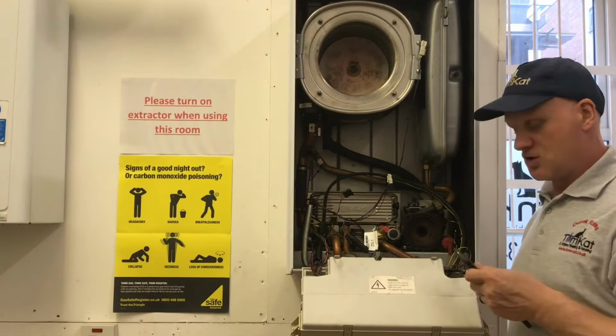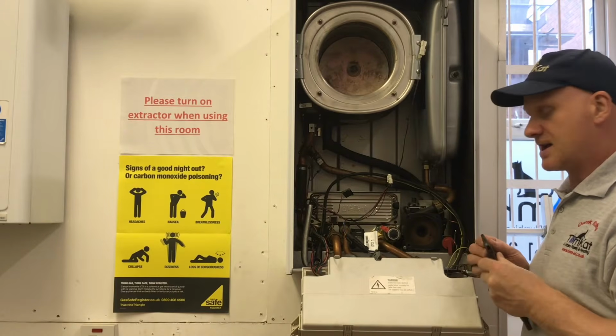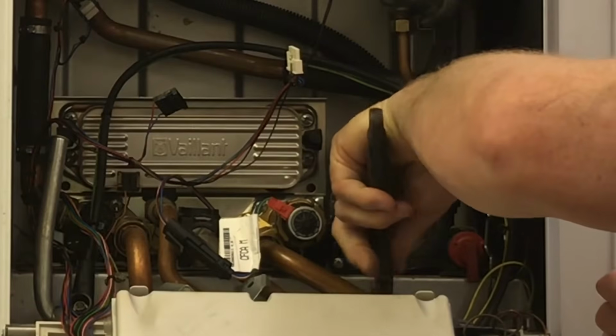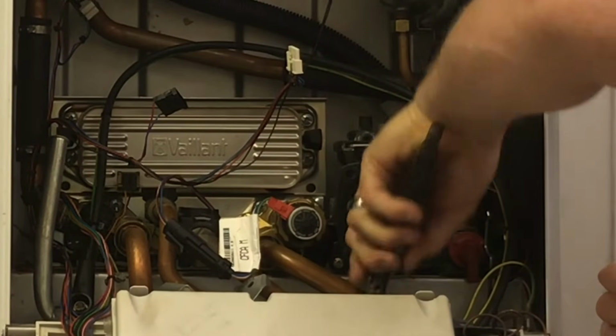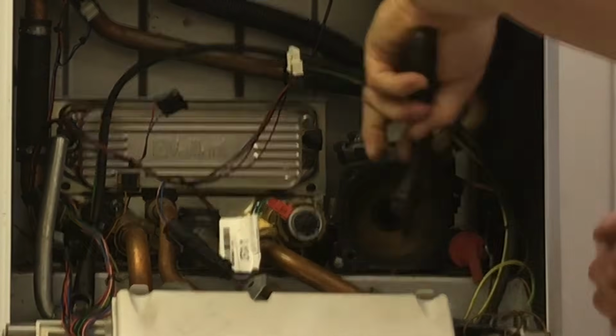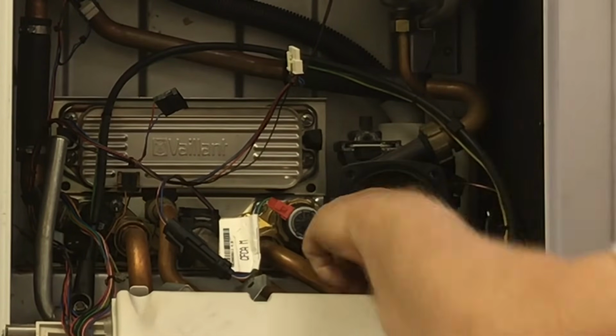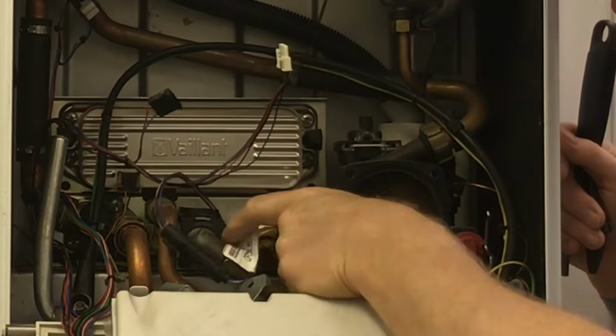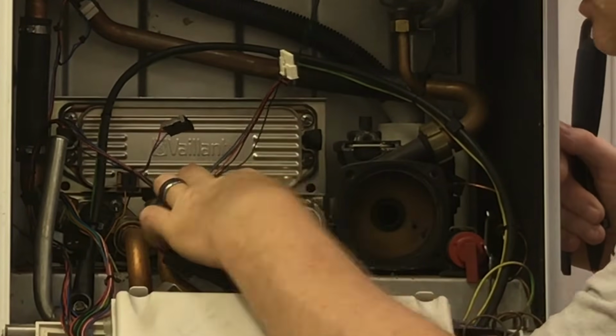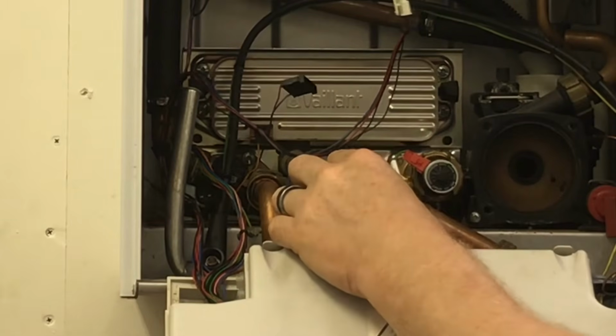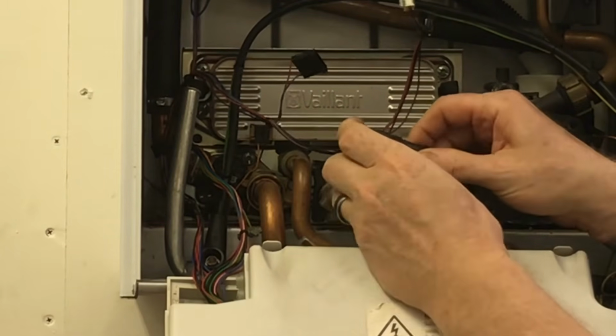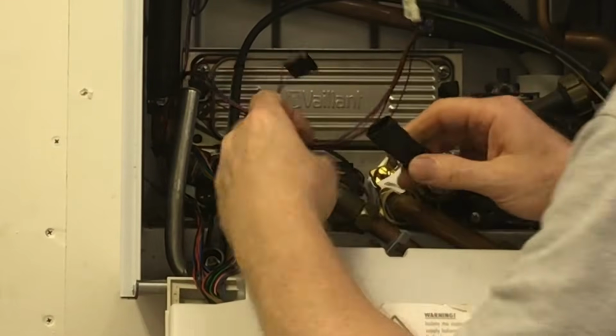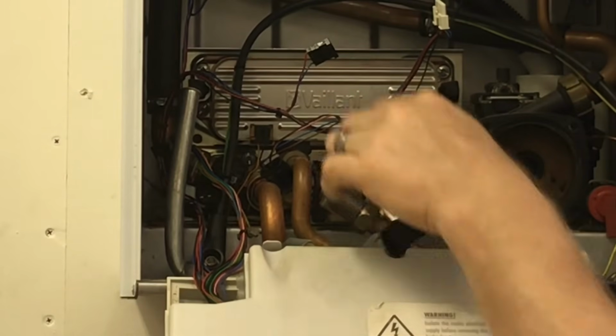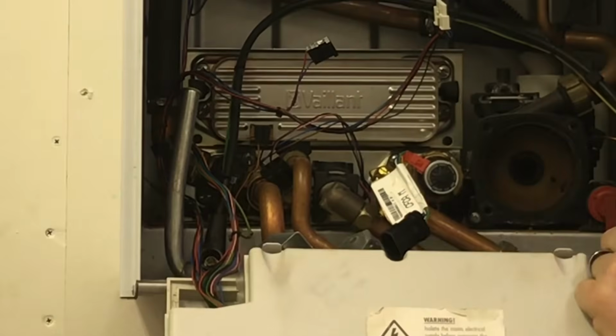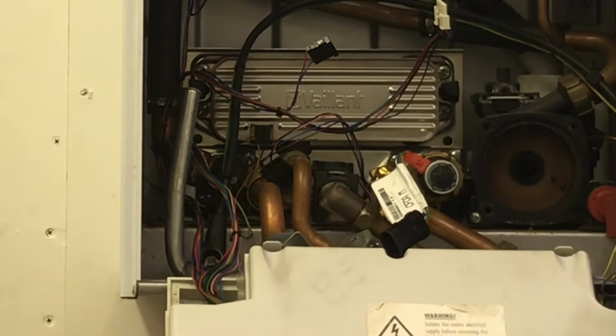So let's first undo this nut here. Again, this is the water set. Again, this is no water. Again, you would have to drain this. So it's a matter of undoing the nut, he says. Inside here is a washer, which we'll need to change. Now we're not going to take the pin out yet, so we're going to leave that off. I'm going to disconnect the wiring. So that's, again, just the clip, he says. Just undo that clip. Okay, I'll explain the difference in these in a bit, so we'll see that in a bit. So I need to get these two, well, 3 screws out now using a screwdriver.